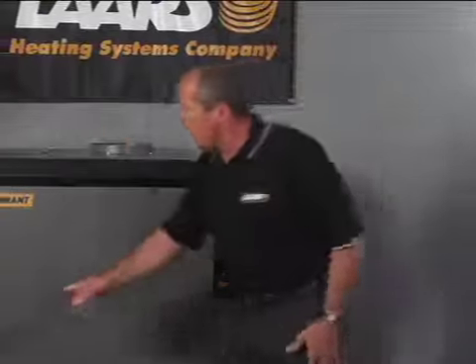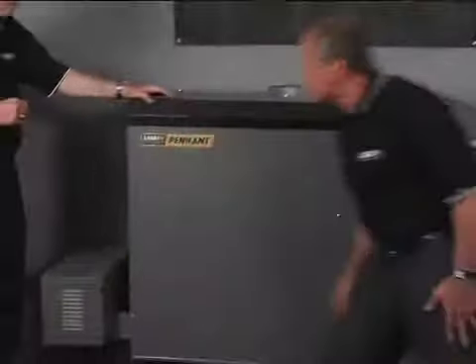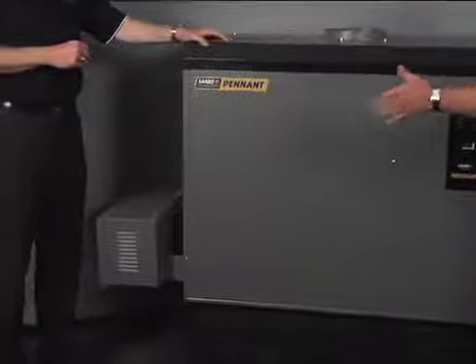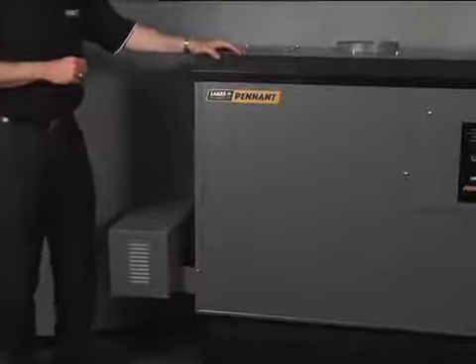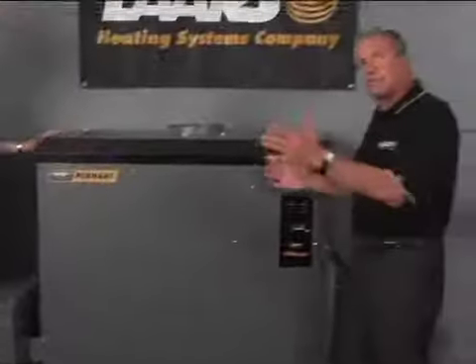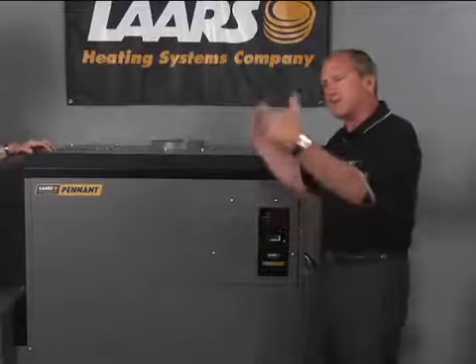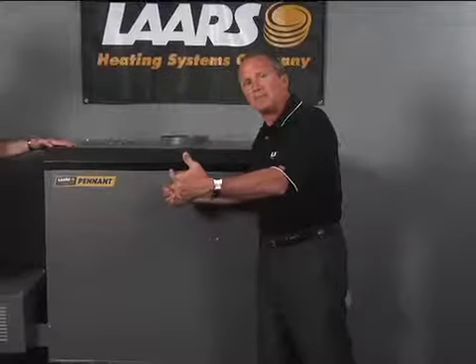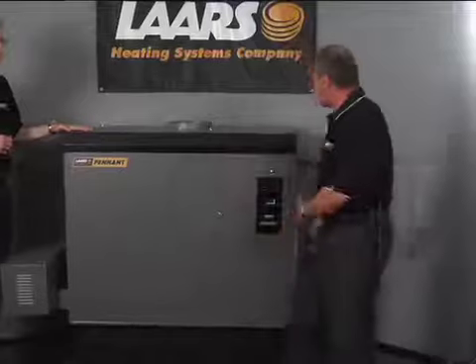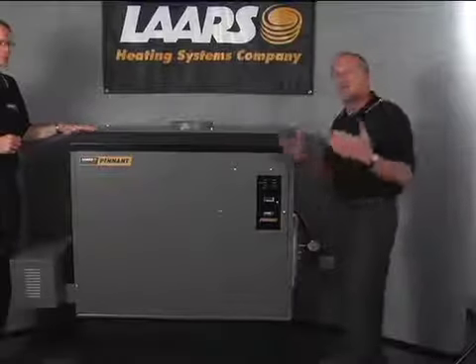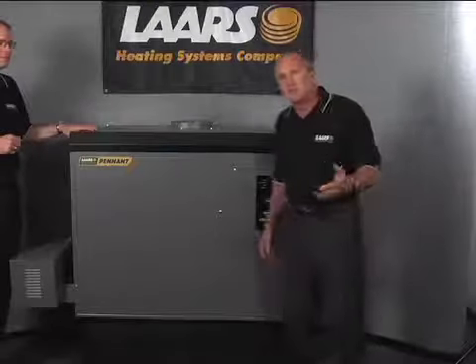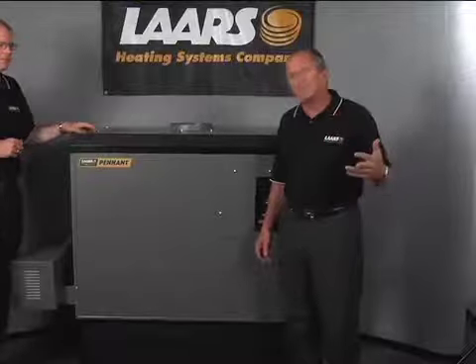Again, as Tom mentioned, one of the nice features here is if you have a pump mounted on that side, you can switch this connection over to this side, and you can put these boilers back to back and have your connections symmetrical from a piping standpoint on one side of the boiler and have your gas come in, so you have a real neat installation, very clean, and very feasible for service as well.